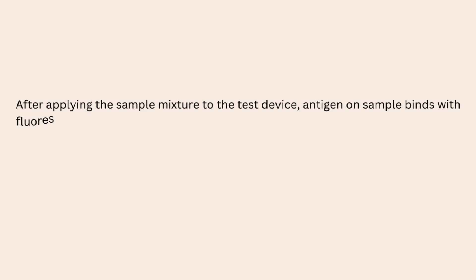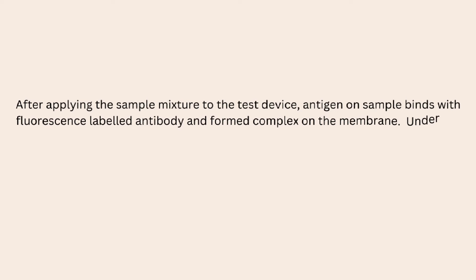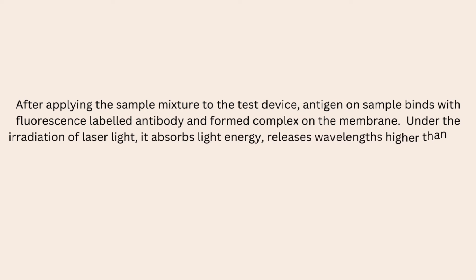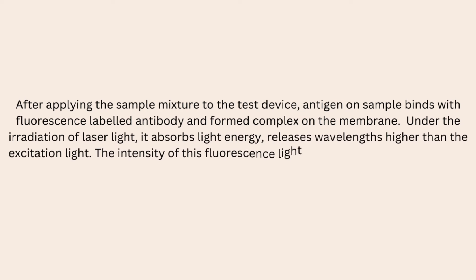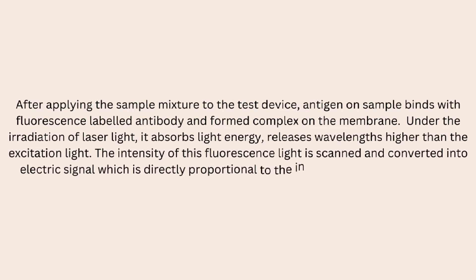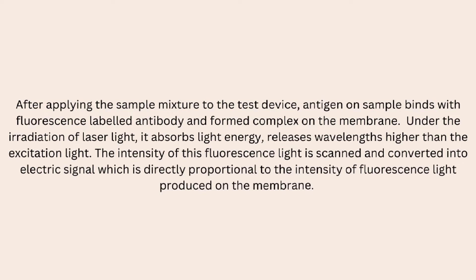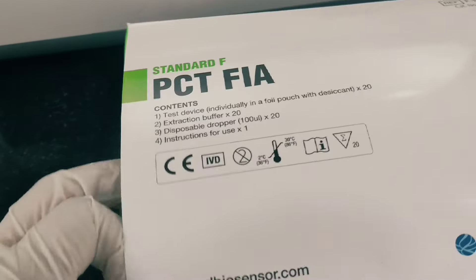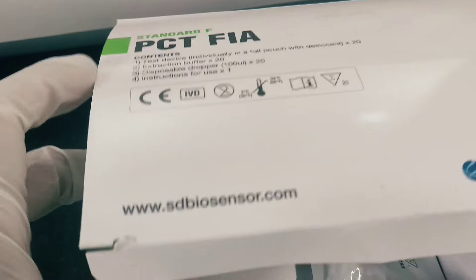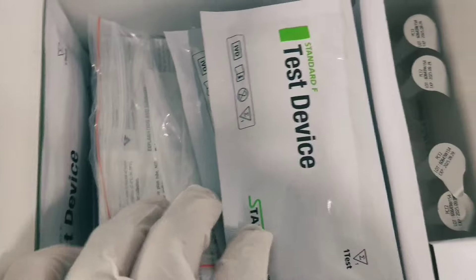After applying the sample mixture to the test device, the antigen in the sample binds with a fluorescence-labeled antibody and forms a complex on the membrane. Under the irradiation of laser light, it absorbs light energy and releases wavelengths higher than the excitation light. The intensity of this fluorescence light is scanned and converted into an electric signal, which is directly proportional to the intensity of fluorescence light produced on the membrane.